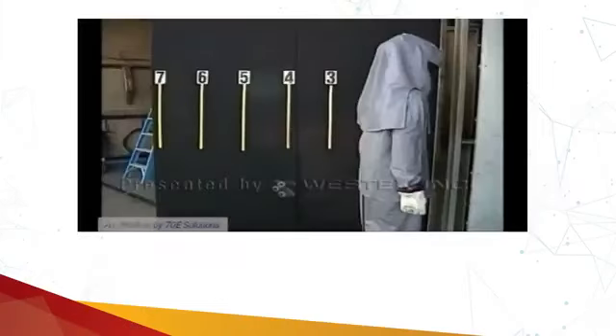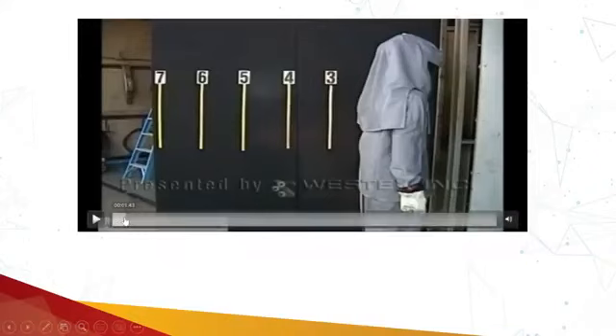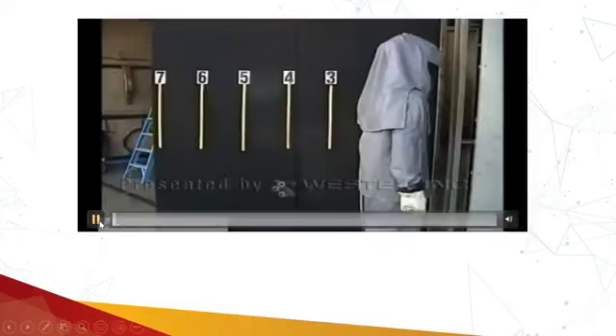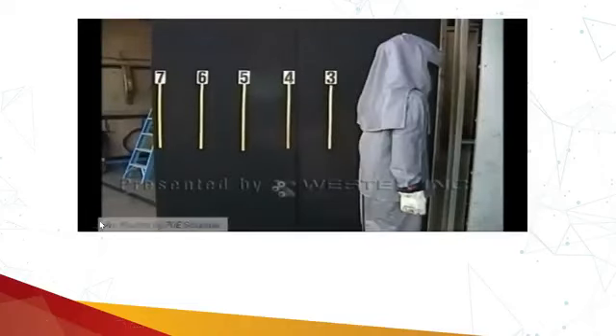This is a motor control center. Okay, let's view another video related to this arc flash event. Now this person is wearing the right personal protective equipment (PPE) for this amount of incident energy available at that particular location. This is a motor control center and a category 4 arc, 35 calories, 15 cycles.